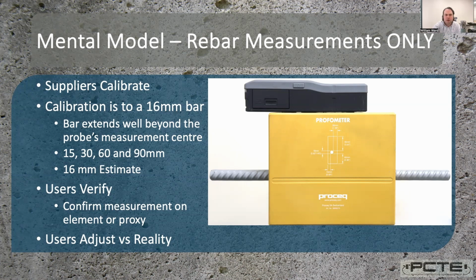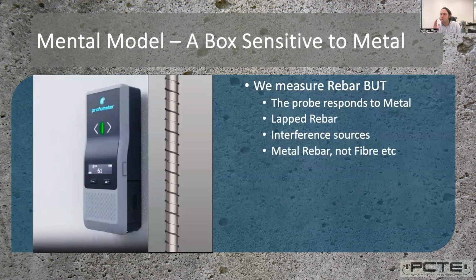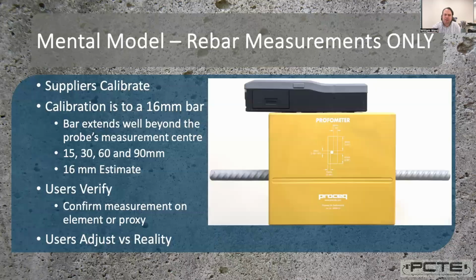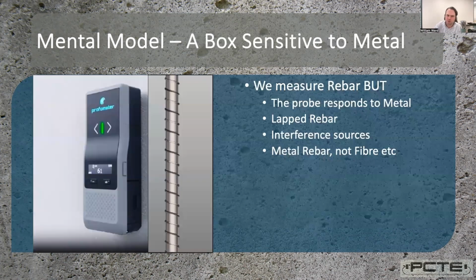So, continuing with our mental model, the other thing to stress is this adjustment is on a 16mm reinforcing bar. And if you build a proxy, that should be a reinforcing bar proxy. This is not a tool to locate post-tensioning. It's not a tool to locate other objects. The way that the conversion from signal strength to bar depth is calculated is built on bar depth. The references are all reinforcing bars. They're not other metallic reinforcing. So measurements to embedded railway, steel, post-tension tendons, anything obscure or esoteric, you'd have to at least build a proxy, and it'd be more of a pass-fail test than a direct measurement for those materials.